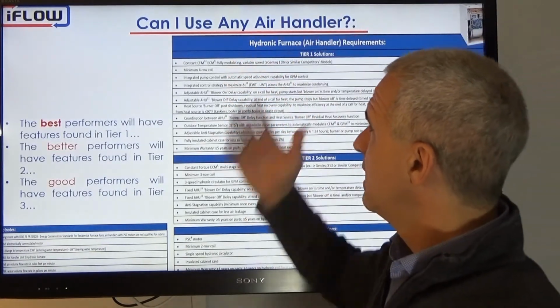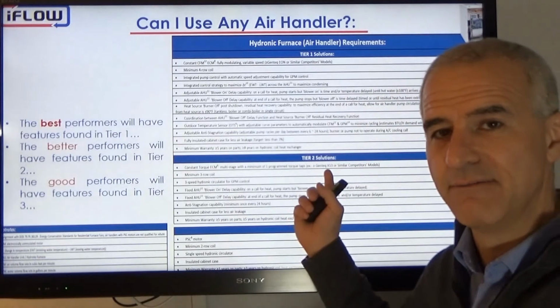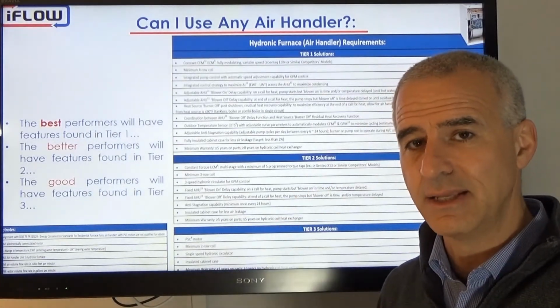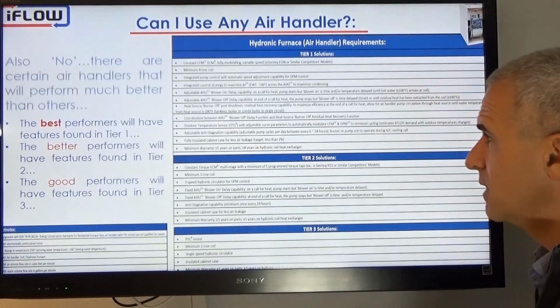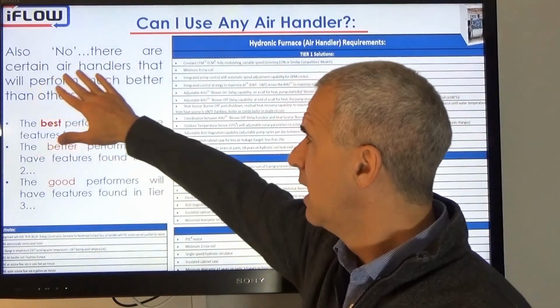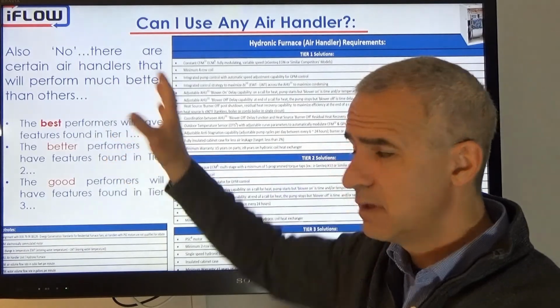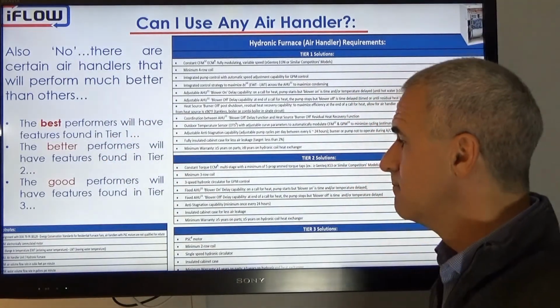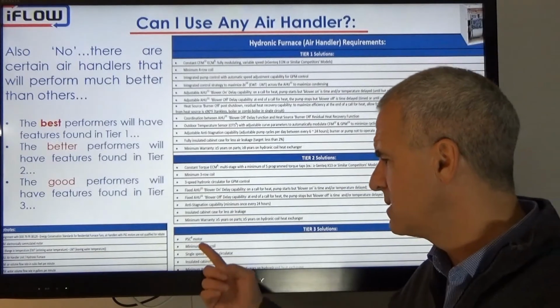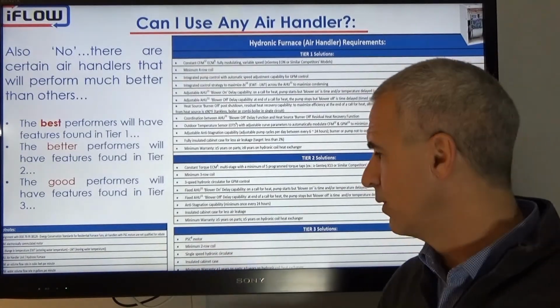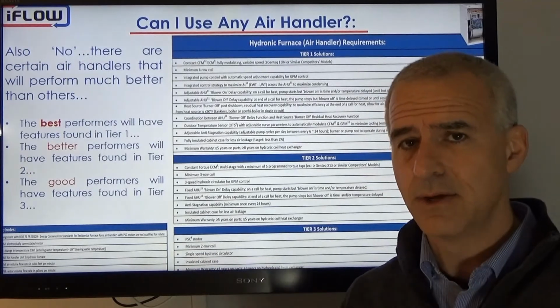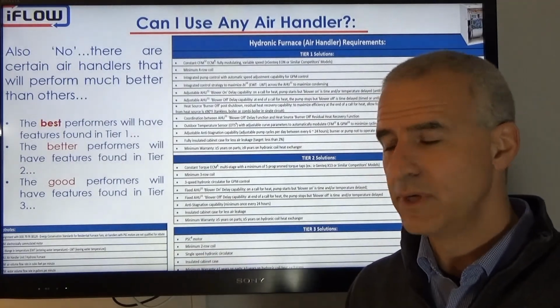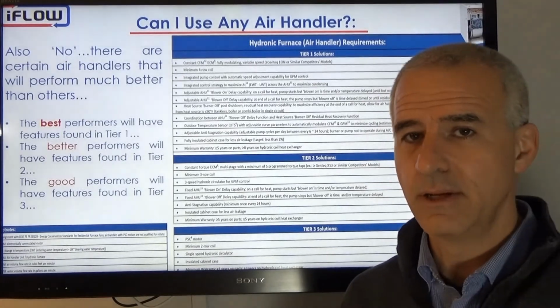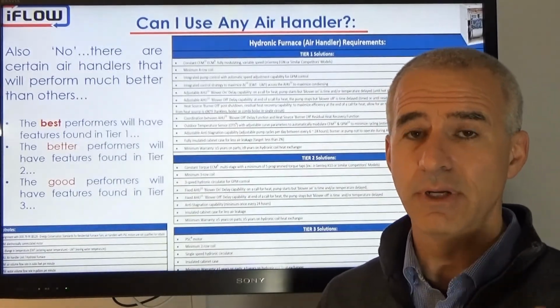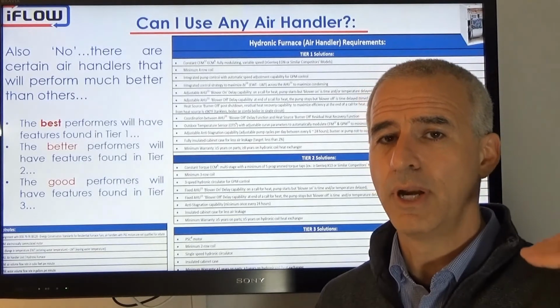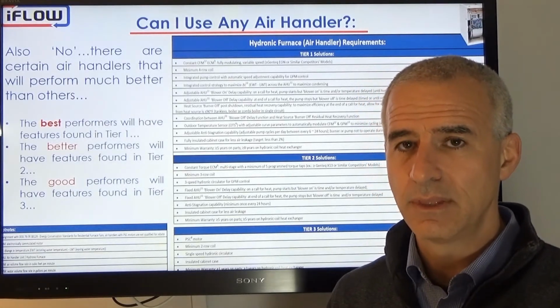So can I use any air handler? Well, it should be obvious that if they don't have that communication capability or that functionality, they really won't be able to perform the same. The answer is no. There are certain air handlers that will perform better than others. I can tell you right now, if it's a PSC motor with a 2-row coil or a 3-row coil with no delta T control, no temperature control, no outdoor reset, you are never going to hit anywhere near 90%. I would say you're not even going to hit anywhere near 80%. You're going to be operating in the mid 70s, even with the Navien.